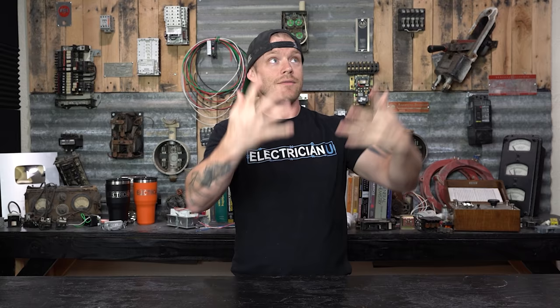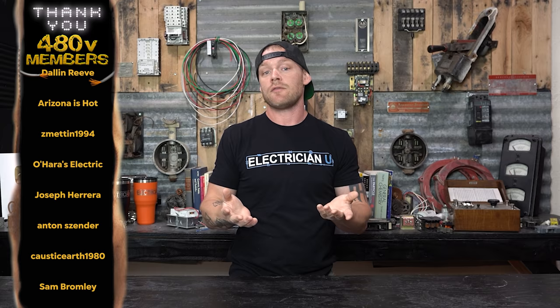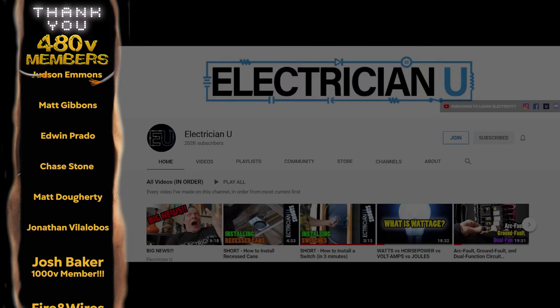That's pretty much it. A simple video, but people have asked how do you even know if a breaker is bad. A lot of times when an electrician walks up to a panel you can open it and know immediately because of the brand, the types of breakers, or the location they're installed in. Sometimes you can't tell a breaker is bad until you pull out a multimeter, and sometimes you have to go even further — take the breaker out and find the bus is messed up, or flip the breaker around and find it's melted on the back. Things that from the front you'd just have no idea about.